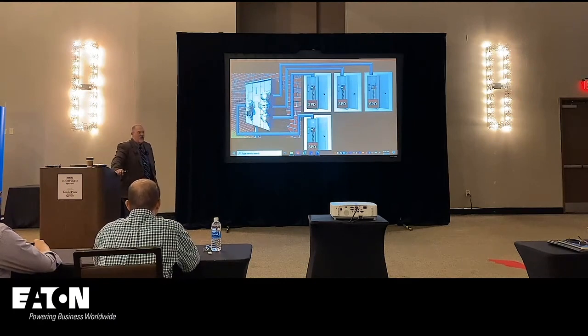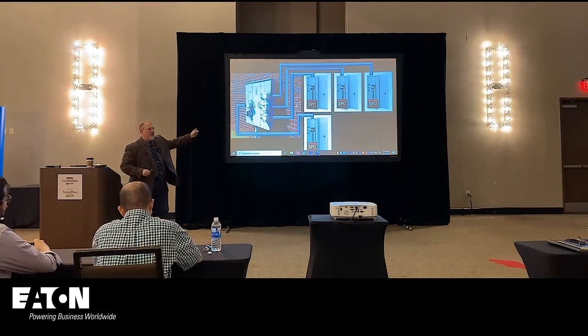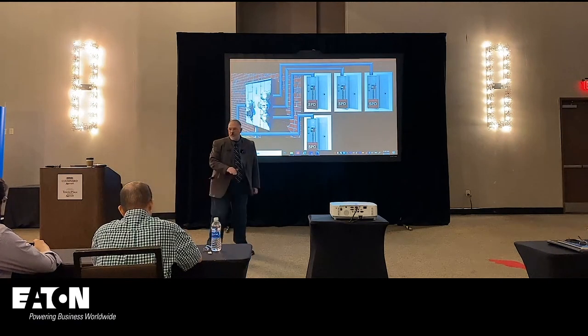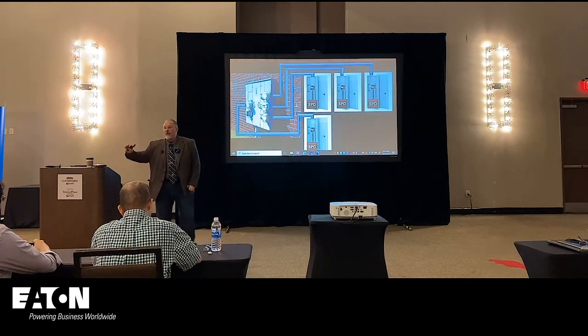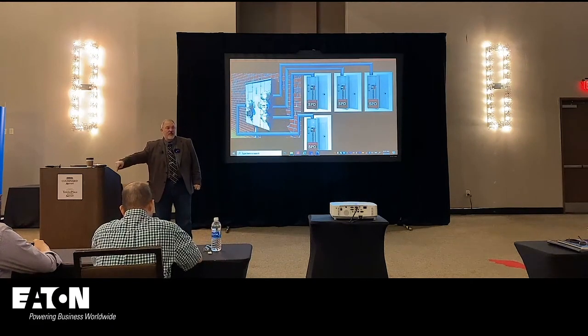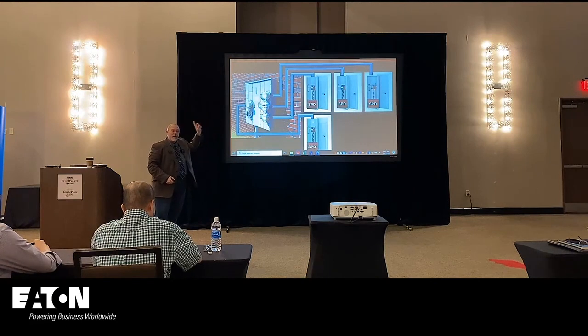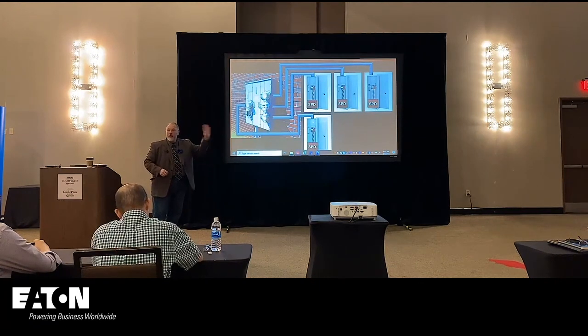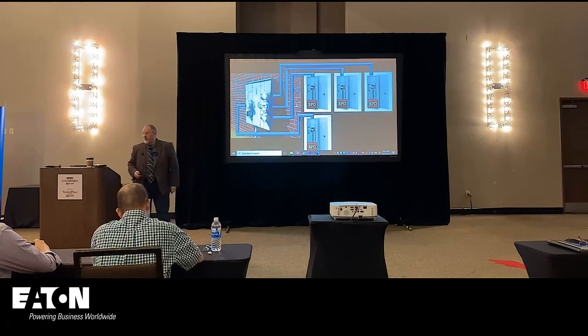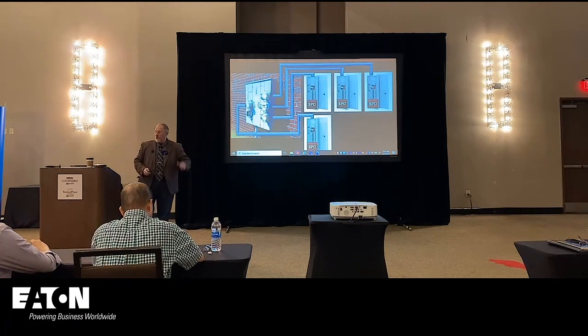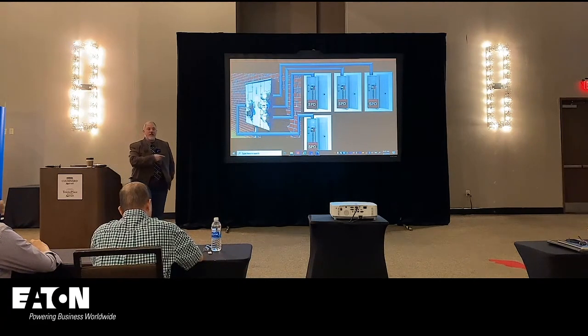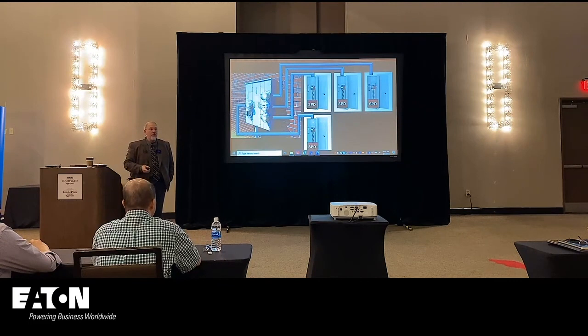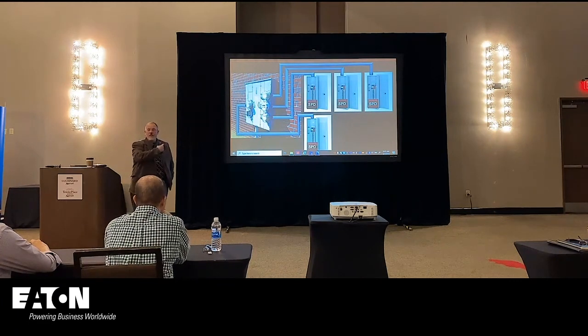But now the other application that we saw was in some cases off of that meter stack, they were coming off with a breaker and going to an HVAC unit outside. And they said, well, do I need to have it on that HVAC unit, or do I still need to put it in my service equipment? If you feed anything, it says in the code, all downstream equipment, whether it be an HVAC unit or panelboards or whatever you're feeding from that structure, from that service, you have to have it at all the locations downstream. So if you have something on the outside and you're taking a breaker off of that to feed, say, an HVAC unit, you either have to have surge in that service or down there at the HVAC unit to be complete and meet the code.